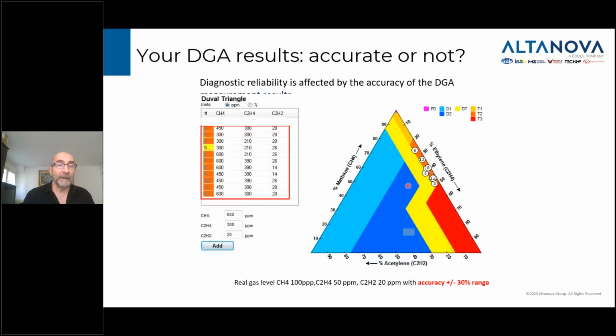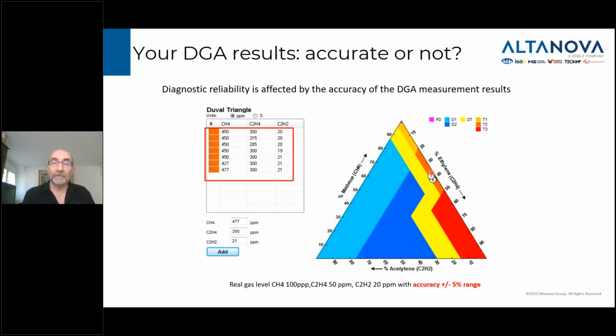Here's another example, with a much higher gas concentration measurement and the same system accuracy of 30%. Here you can see a lot of the diagnostics fall into a D2, a T2, which is mostly thermal fault between 300 and 700. Some of them are very close to arcing, and some of them are in the DT. You take the same sample, you put it in a system with an accuracy of 5%, and now mostly all of them are concentrated into a T2 diagnostic. So this is the impact, especially when you're using the Duval triangle. You can see that it really concentrates the diagnostic in a much tighter area if you go from a very low accuracy to a very high accuracy system.